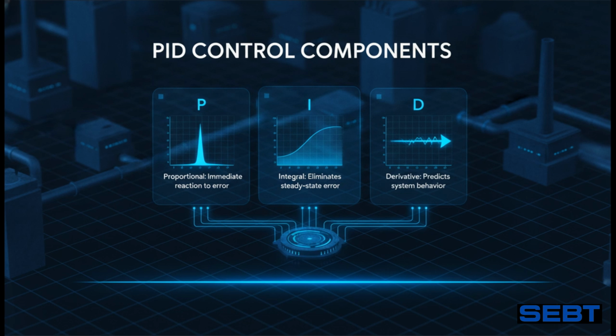P stands for proportional. Think of this as the immediate reaction to the current error. If a door suddenly swings open and a huge rush of hot air comes in, the P reacts right away. I is for integral. This one looks at the past. So if we're stuck, say, half a degree away from our set point for a long time, the integral component slowly builds up and pushes to eliminate that stubborn steady-state error.